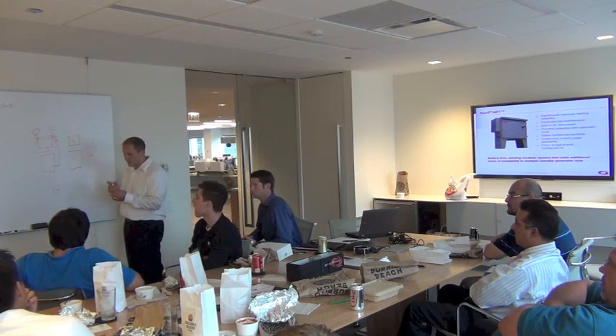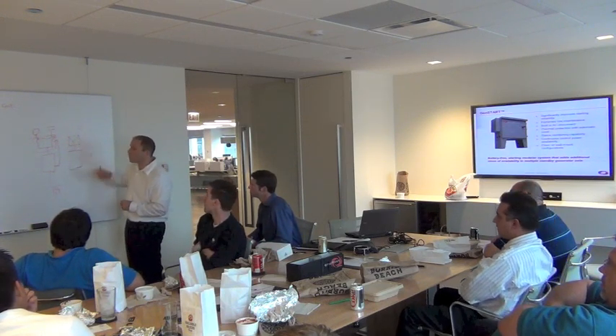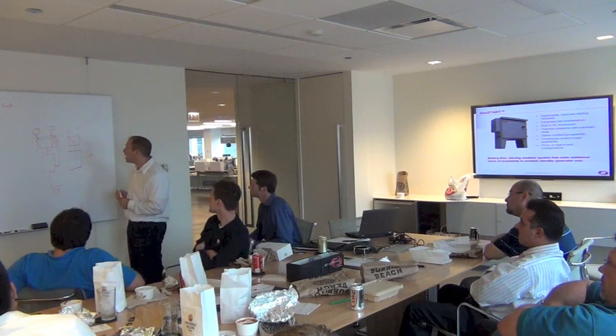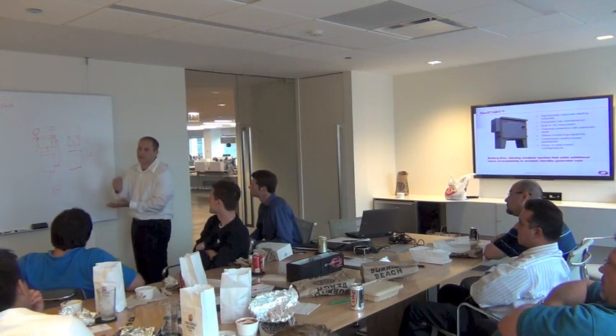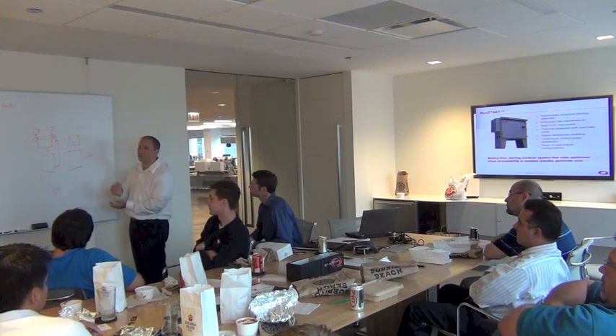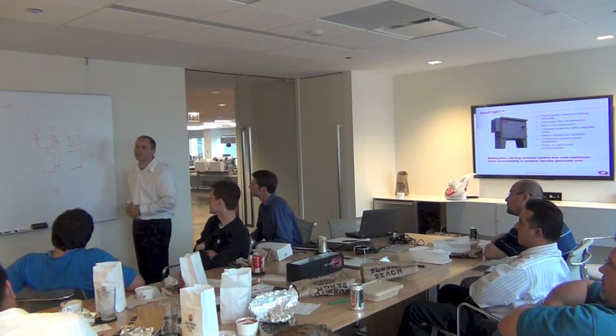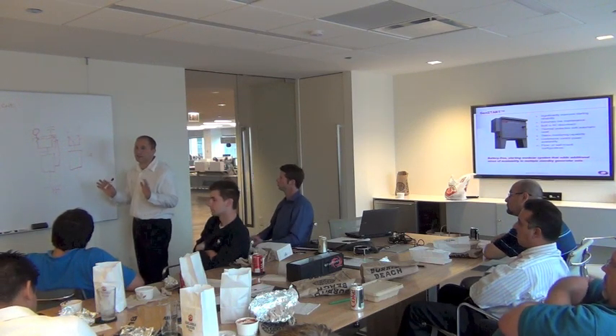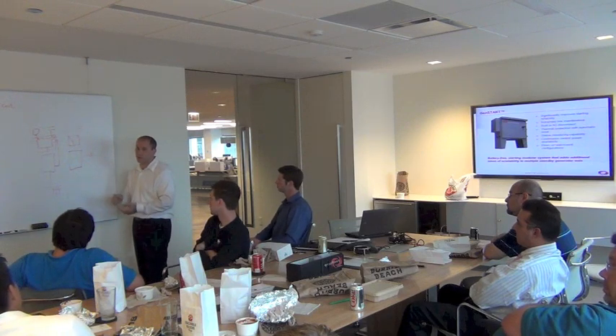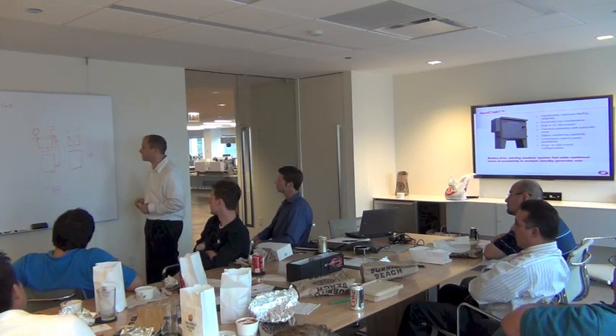And it's important when using flywheels, even if you do have a transfer switch with over and under voltage detection. What if you're getting a bunch of short-term hits and you have a program to transfer after 1 second, but you're never getting a full 1 second outage, and you may be depleting your wheels? So this is a nice feature to say, hey, for whatever reason, utility is unstable or in the process of failing, we want to go ahead and start the transfer process. So it's a nice integration feature.